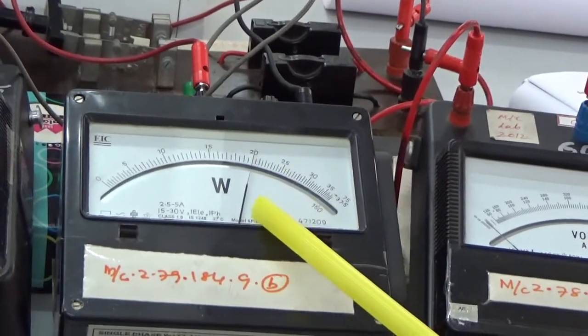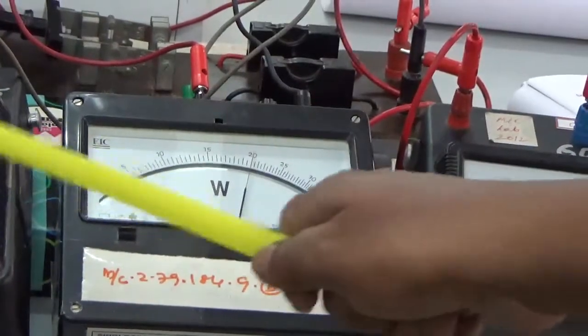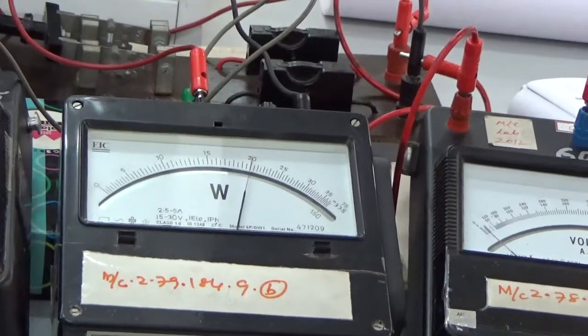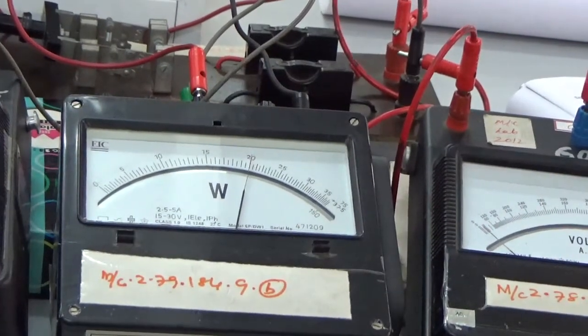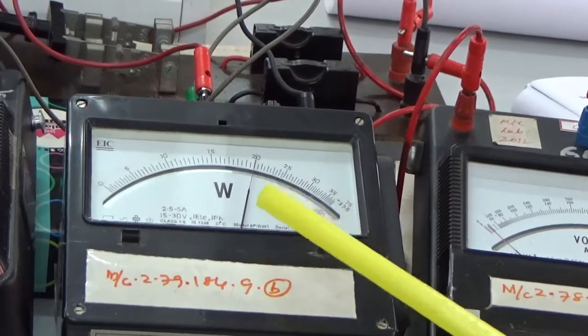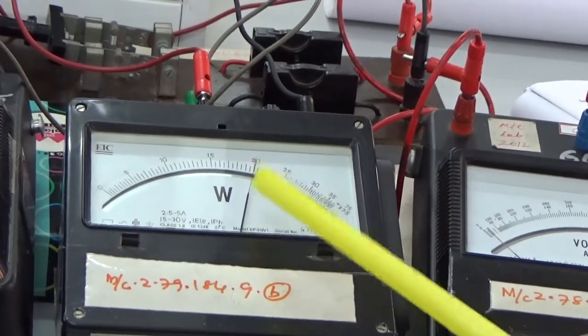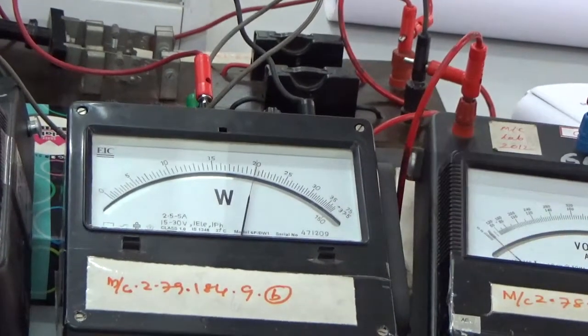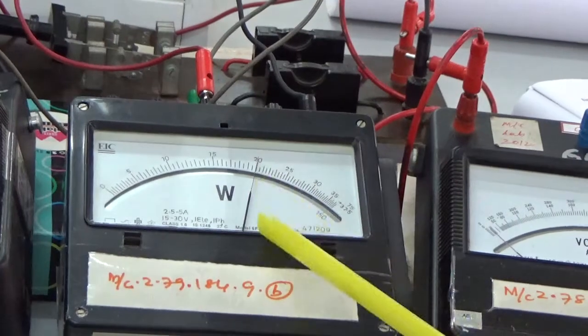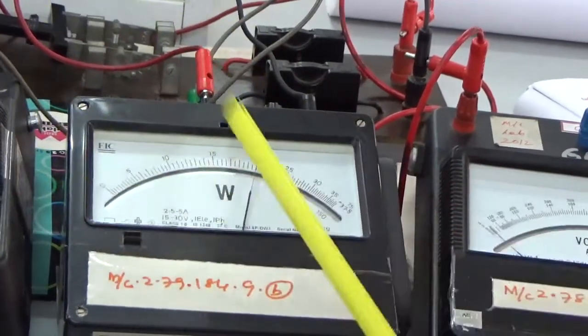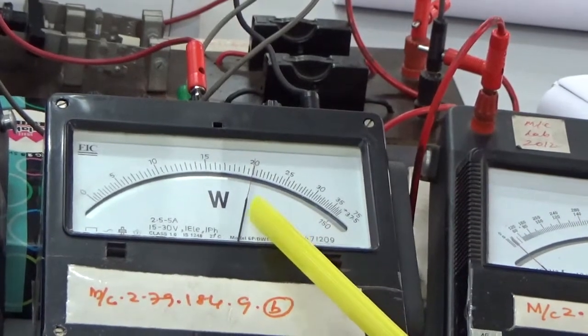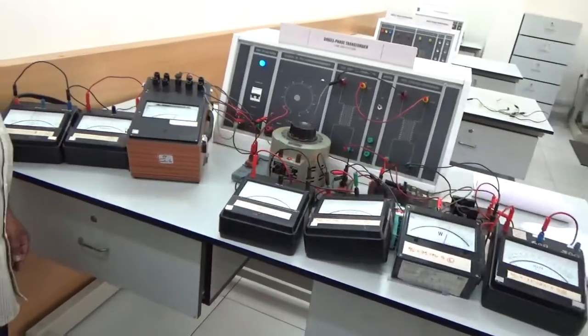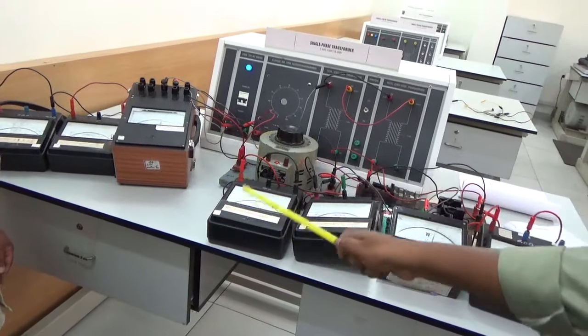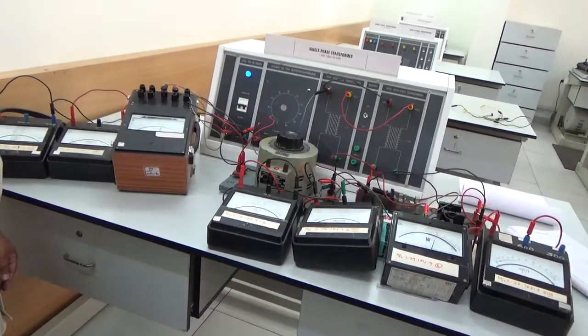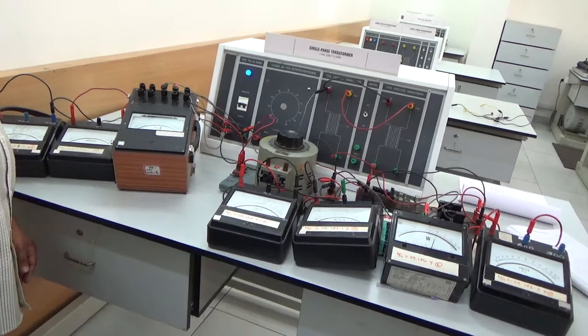This gives the copper losses, the I square R losses, that is the short circuit current squared times the resistance of the windings of the two transformers. So this wattmeter gives the total copper losses in the set. If I want to calculate the efficiency of the individual transformer, I have to divide this wattmeter reading by 2, and likewise the iron losses of the set divided by 2 give the individual iron losses. Once I know the iron losses and copper losses of the individual machine, it is easy to calculate the efficiency of the individual machine.